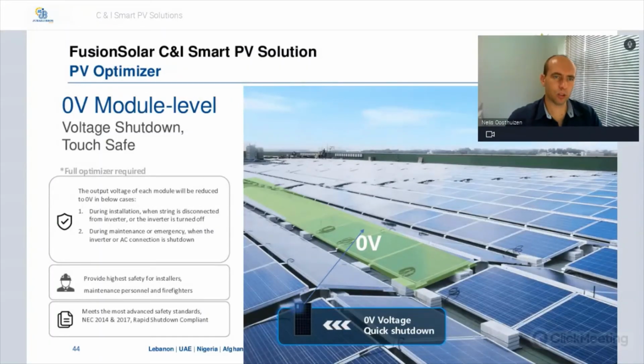So 0 volt module level voltage shutdown, touch safe, that's the rapid shutdown that I've mentioned. The output voltage of each module will be reduced to 0 volt in the below cases: during installation, when the string is disconnected from the inverter or the inverter is turned off, or during maintenance or emergency, when the inverter or AC connection is shut down. This provides high safety for installers, maintenance personnel, as well as firefighters.